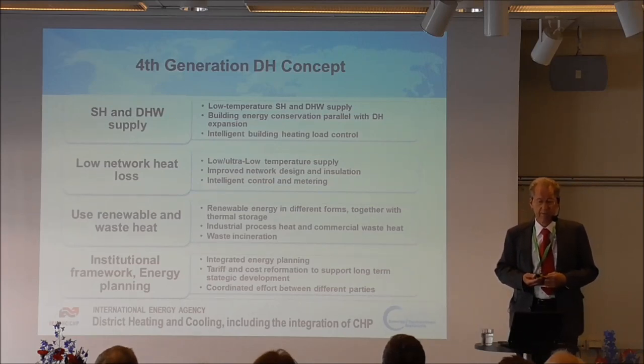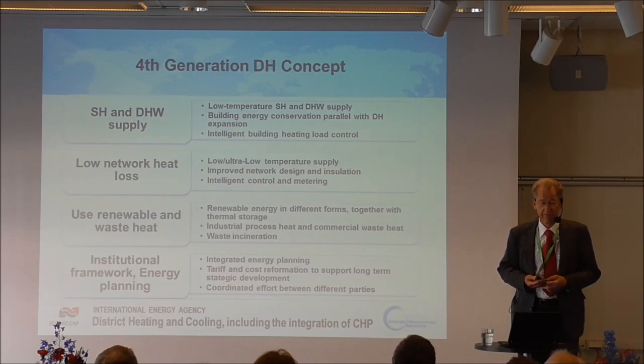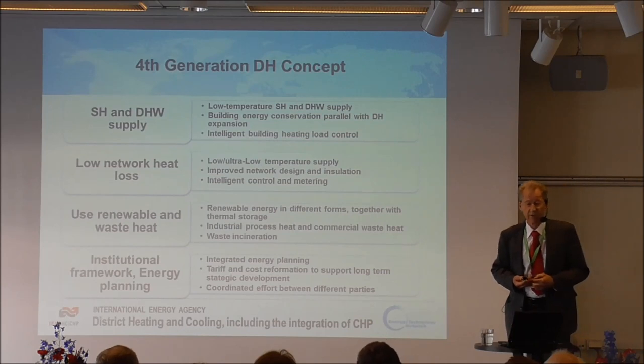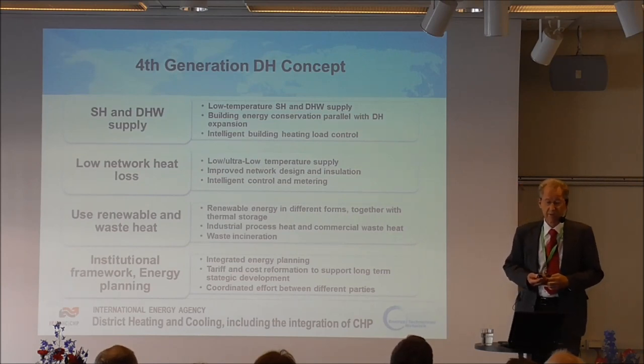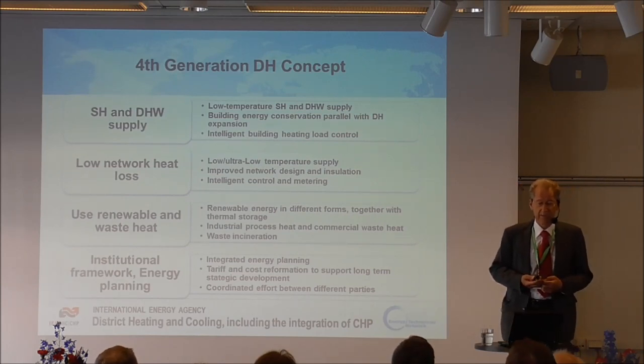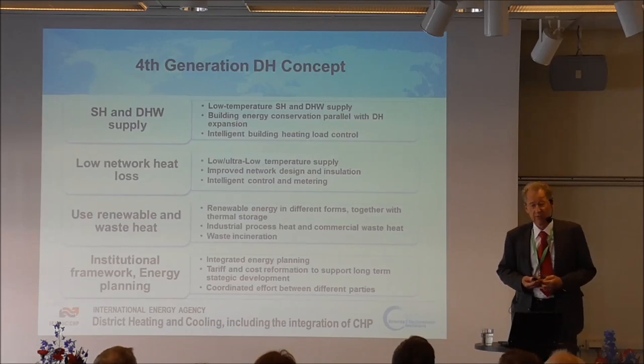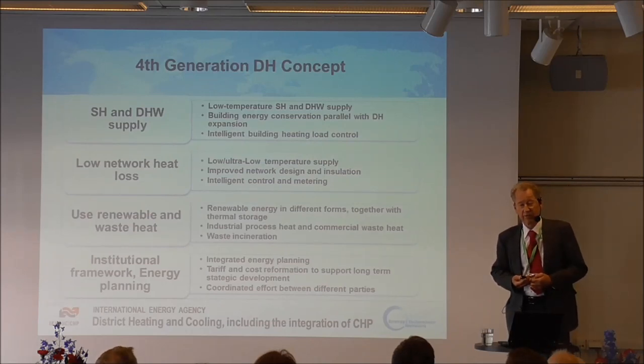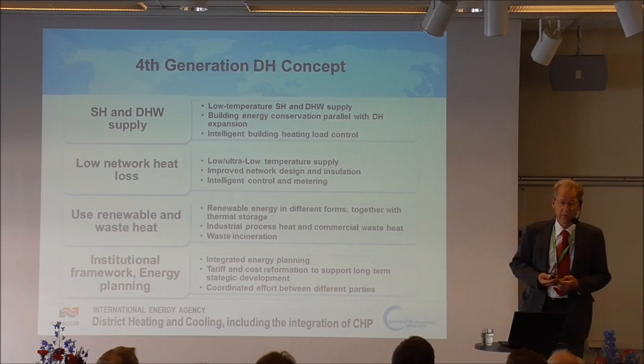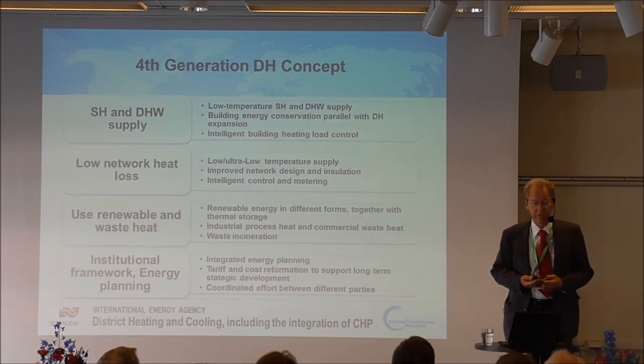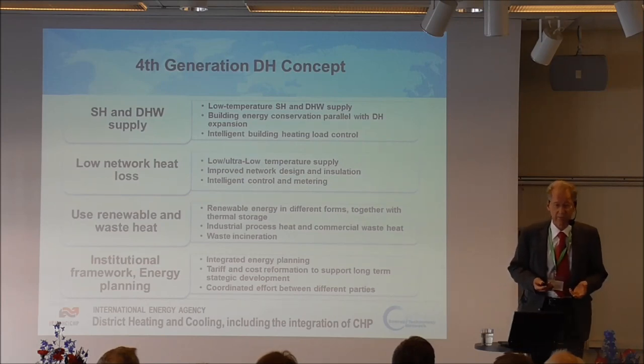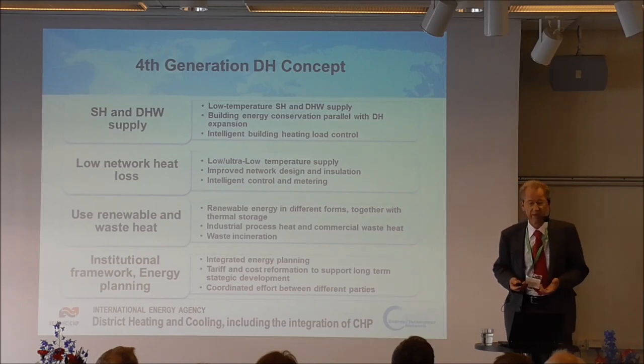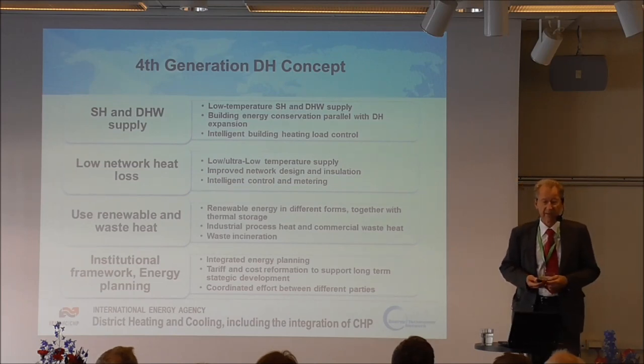Low temperature - 55 degrees in supply, 25 in return, or even lower - combined with heat pumps and electrical supplementary heating, is one way to lower the heat loss. If you can have a temperature difference to the ground which is only half of what we typically have today, the heat loss will be halved. That's readily available and can be done in existing systems.